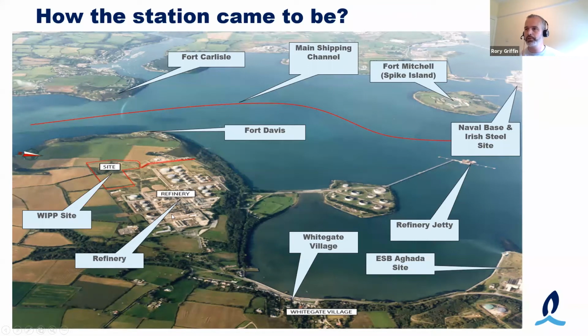Just some other points to note here. Having a refinery next door to us is very handy. In the Irish Grid Code, a gas-fired station such as Whitegate or the other CCGTs have to be dual fuel. So in the event there was an issue on the gas network, the units would be expected to switch over to secondary fuel. This would help retain the gas pressure for domestic customers as well as business customers. So the site itself was quite handy.